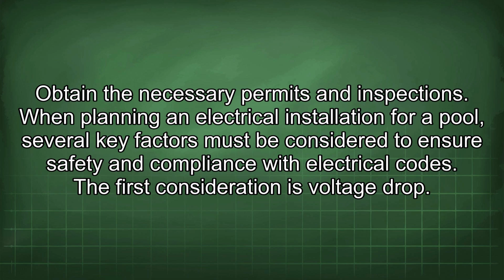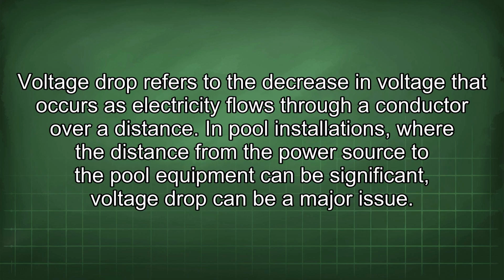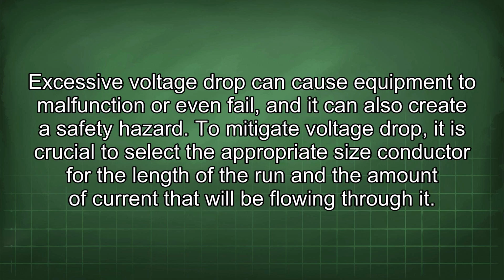When planning an electrical installation for a pool, several key factors must be considered to ensure safety and compliance with electrical codes. The first consideration is voltage drop. Voltage drop refers to the decrease in voltage that occurs as electricity flows through a conductor over a distance. In pool installations, where the distance from the power source to the pool equipment can be significant, voltage drop can be a major issue. Excessive voltage drop can cause equipment to malfunction or even fail, and it can also create a safety hazard.